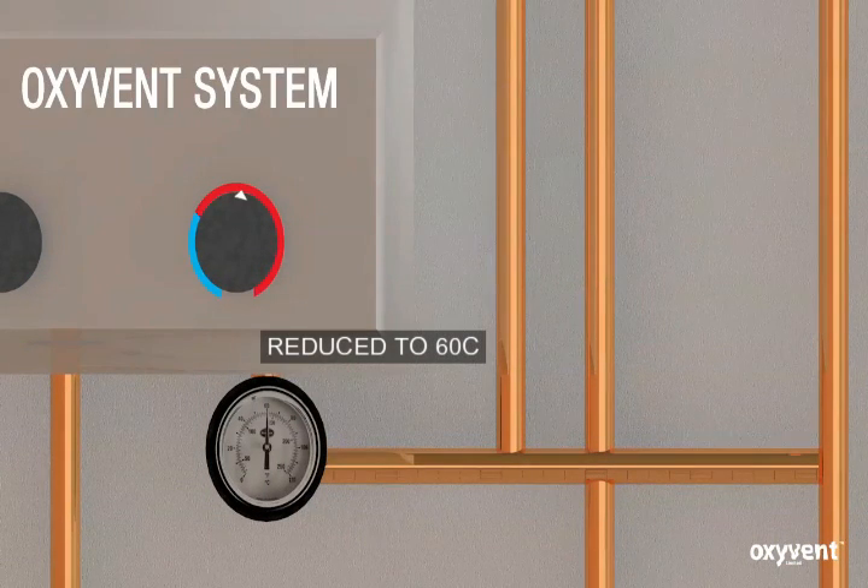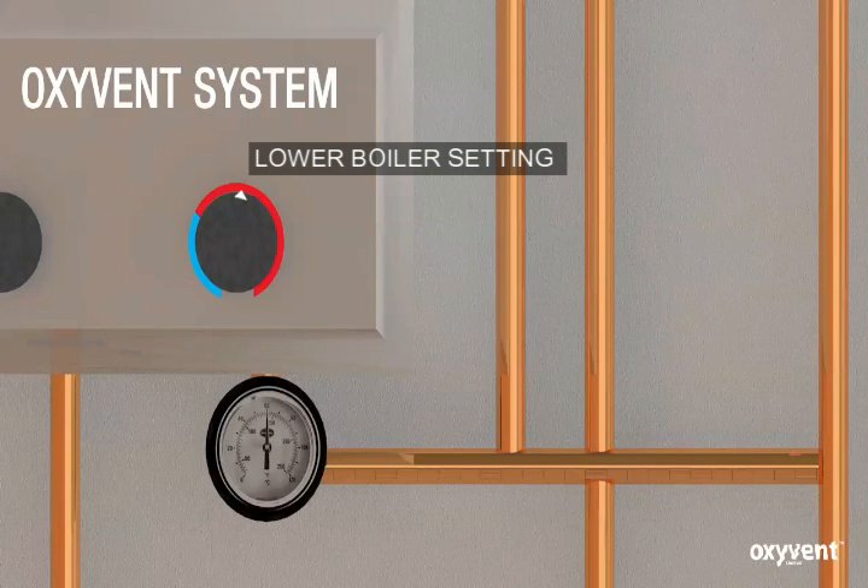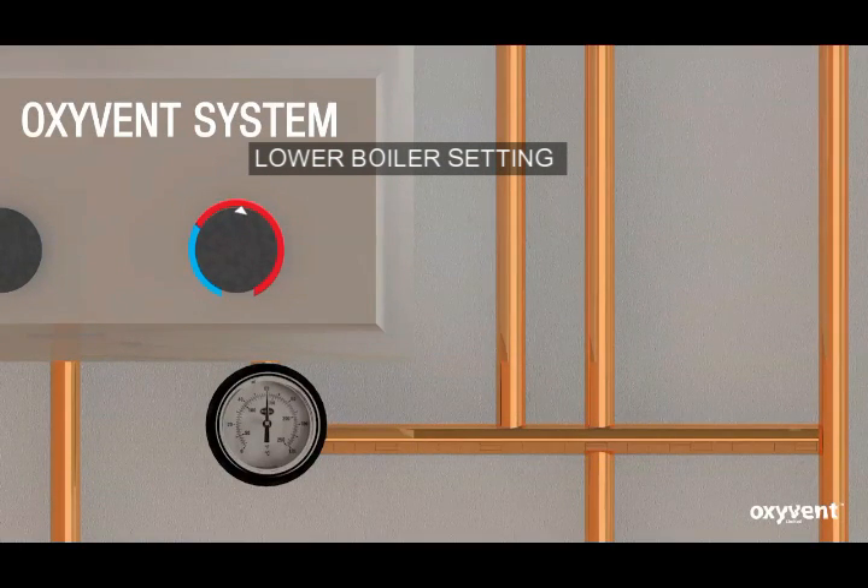The Oxyvent system allows you to reduce your boiler temperature to 60 degrees without sacrificing your comfort. Oxyvent keeps your condensing boiler in condensing mode 100% of its operating time. This is achieved by keeping the water returning back to the boiler below 55 degrees.